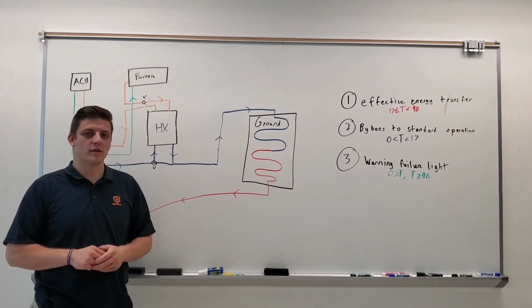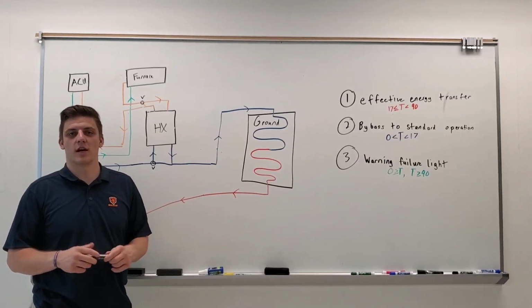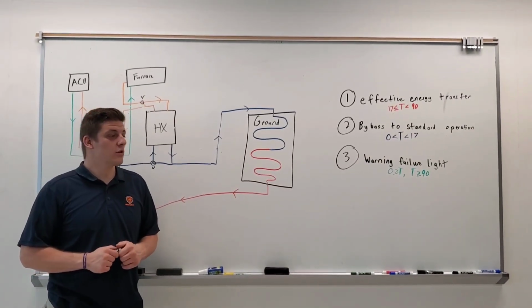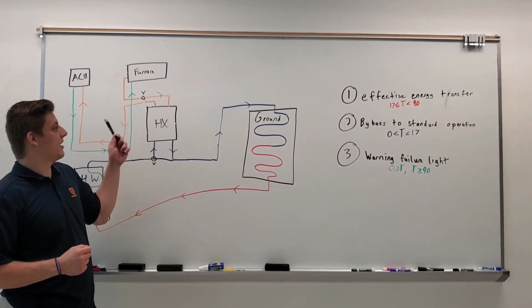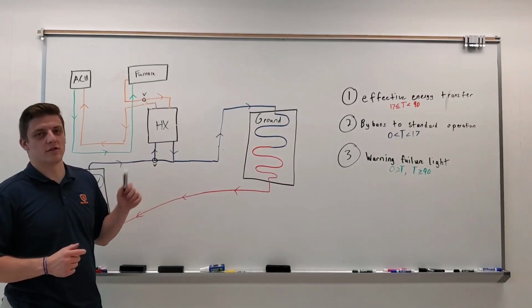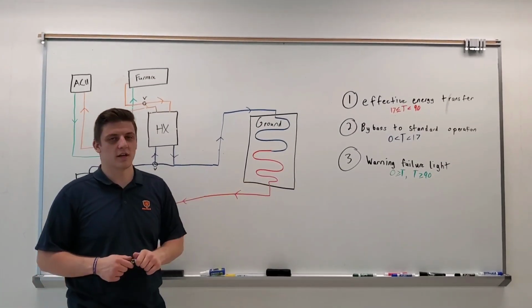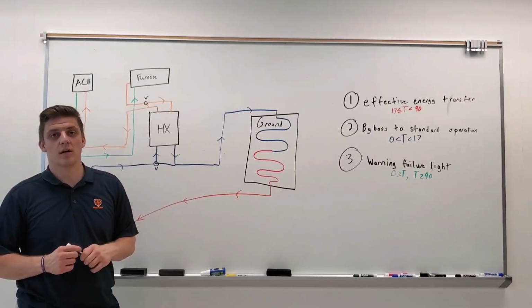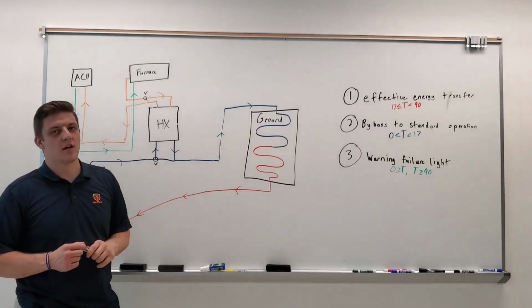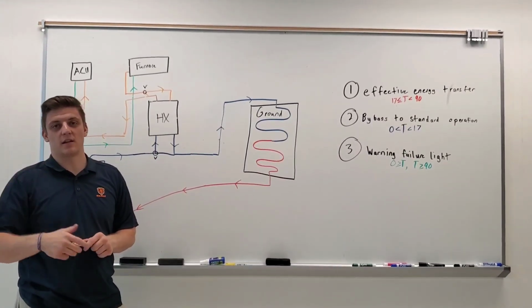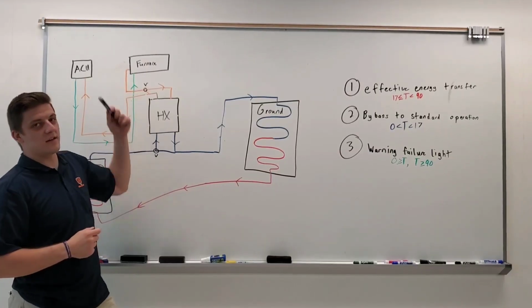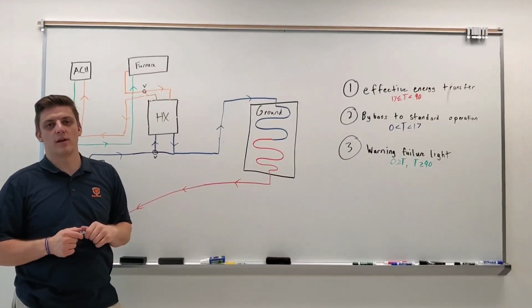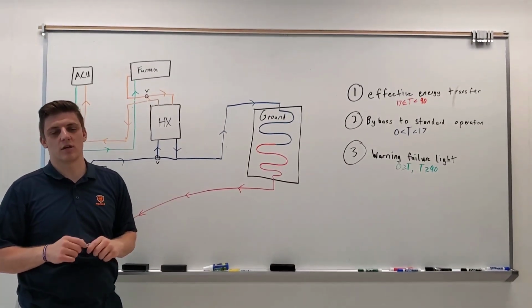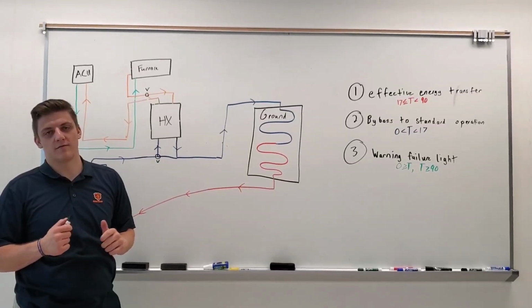So the two things we've learned from this prototype design of our concept were, first off, we need a pressure release valve on our refrigerant loop, because if we hit our warning areas and we need to bypass our heat exchanger, that heat is just going to be cycling through our system. And if our ACU can't handle that, we need some way to release that temperature and pressure so we don't have a failure.